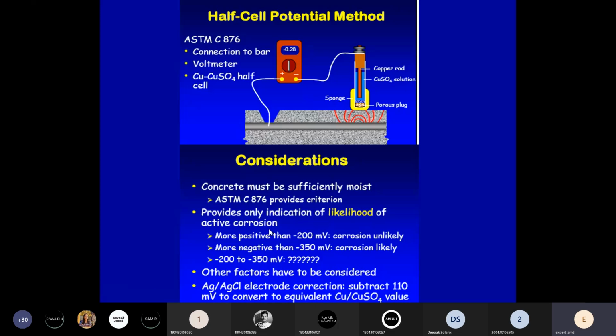If your value is more positive than minus 200 millivolts, it indicates corrosion is unlikely to take place. If it is more negative than minus 350 millivolts, there is a possibility of corrosion. If the value comes between minus 200 to minus 350 millivolts, we are not sure.